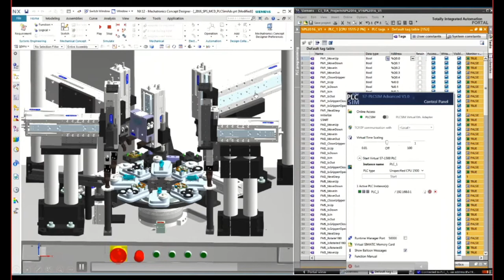On the right, you can see the status of those signals. As things happen, it sends data to the PLC, which then sends directions to make this linear slide move, index in and out, and clamp or unclamp parts as it picks them up and moves them. Eventually, when all the stations are done, it indexes, sending all those directions based on the signal inputs.